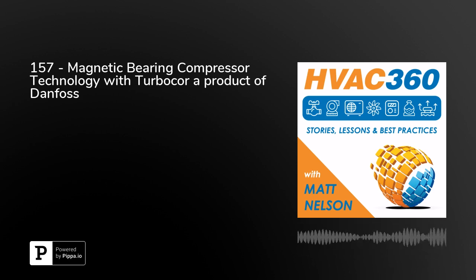But I think a lot of customers are not aware of the long-term benefits. Specifically, the efficiency you get from taking oil out of the system is not only valid on day one, but also 20 years from now. The performance you get when we ship the compressor brand new is essentially the same performance you get 20 years from now, because there's no oil in the system. Several independent studies from ASHRAE have confirmed that it is very common for service technicians to overcharge oil in the system, and whenever you do that, you're robbing performance from the chiller.